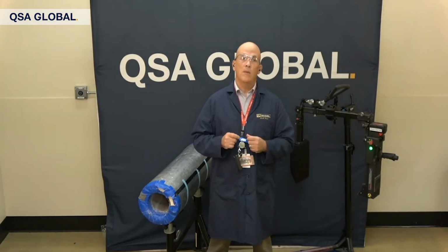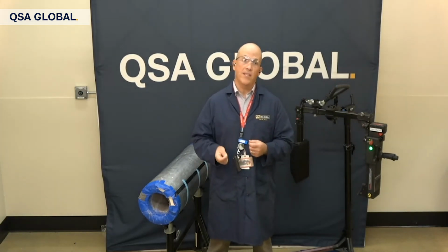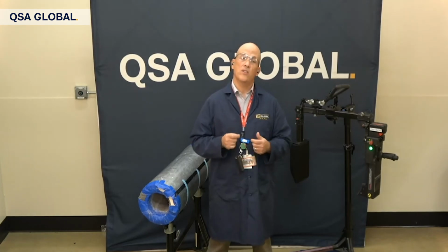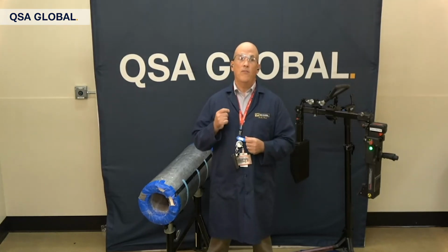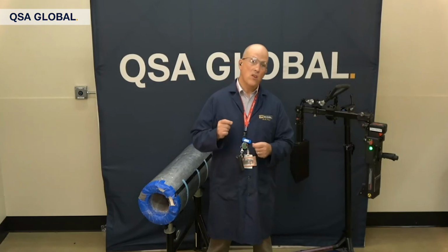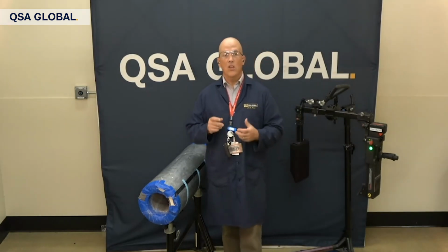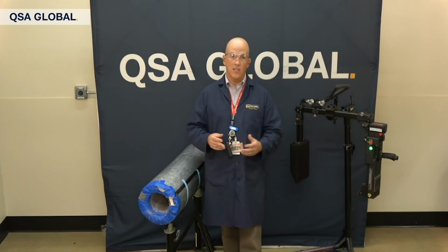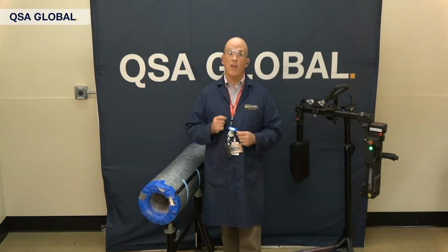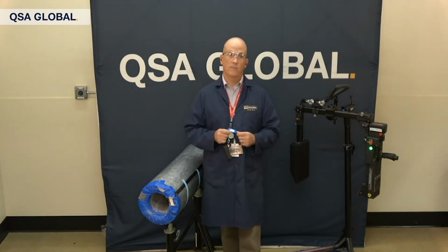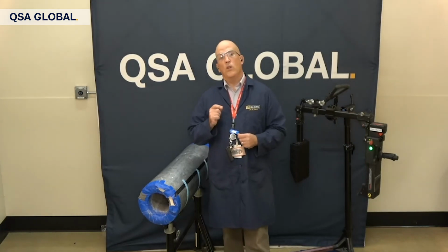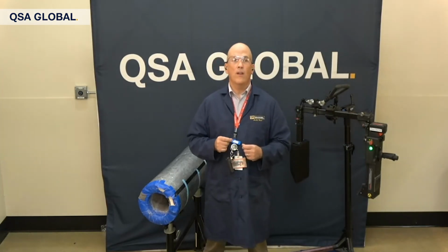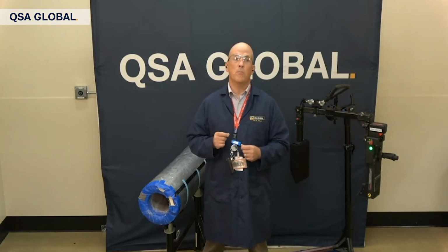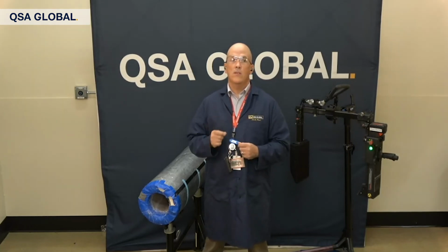For CUI, piping ages, sheathing is not maintained, and the condition of insulation can vary. If you're not sealing up the separations, not making the repairs to the sheathing, your CUI susceptible inventory continues to grow and puts a greater burden on your inspection program. When you have deferred maintenance, you add more issues to manage, which puts the burden on a suite of NDT tools. This is where you must use data and engineering rigor.